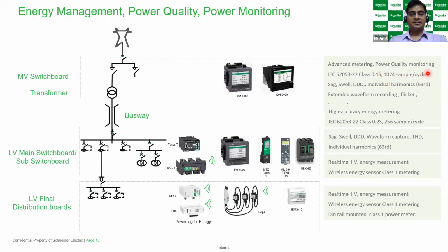In such a case, very good meters have already come into the market, with an accuracy class of 0.1 S and a sampling rate of 1024 samples per cycle, so that you can register that information and finally protect your capital equipment. And from the LV switchboard part, which we call LT panels, there is a dedicated solution inside the metering that you can protect from at the 0.2 S level.